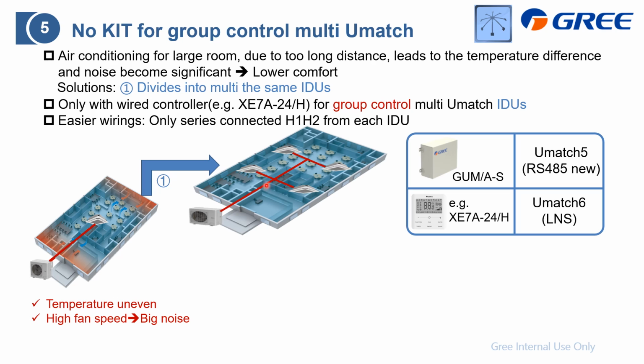And also you can find it is similar to the VRF, right? But the control is not the same, because we need to make all the indoor units completely the same, because there is no EXV inside to ensure the refrigerant can divide evenly. Only the on-off. And also for this one, you need to ensure all the heat exchangers are similar or even the same. And for this one, we can only achieve it by using the same indoor unit. And when we achieve it, you can find we can make the temperature even, and a lower fan speed is also okay.